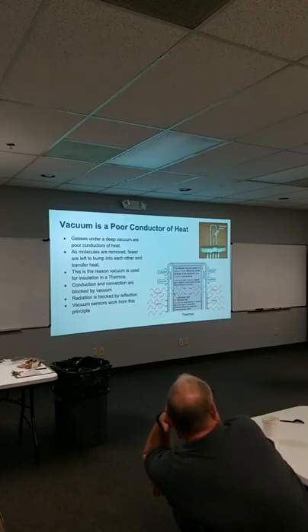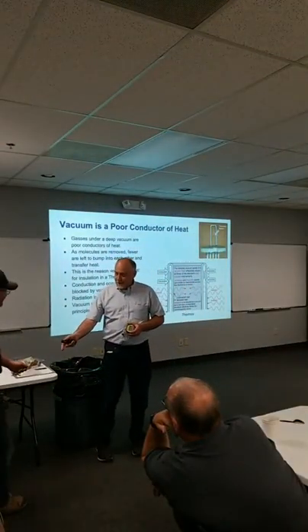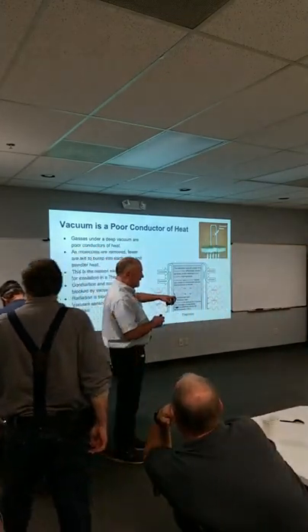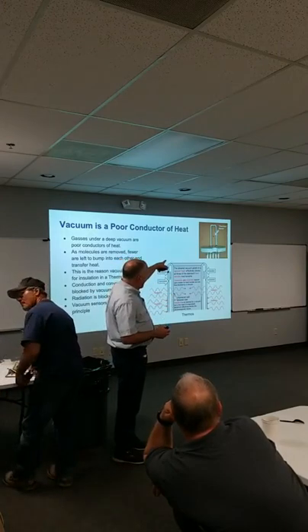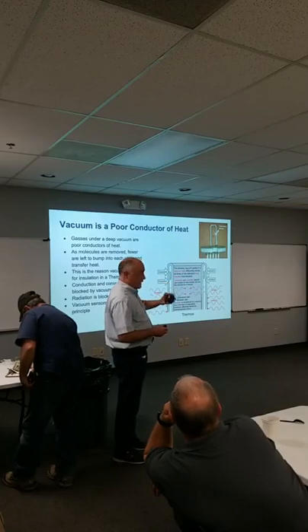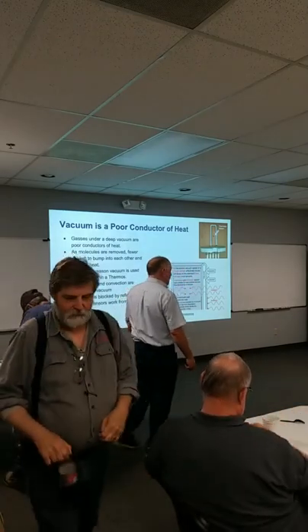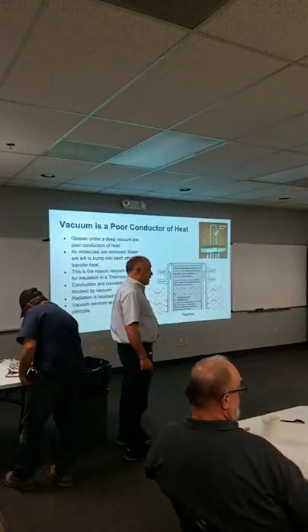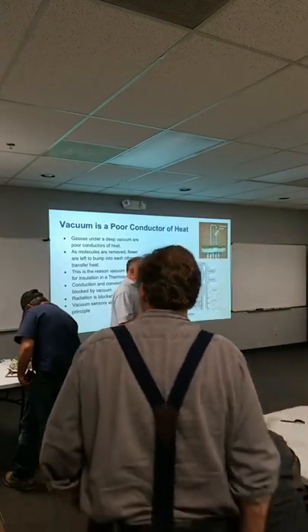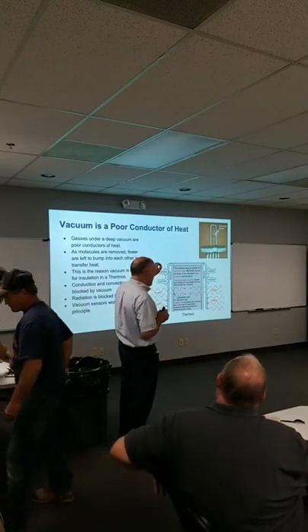Right, so if you're looking, oh, let's see, you brought your dues. Oh, absolutely. Thank you. If you look inside this hole right here, inside the hole is that sensor. If you look just inside here, you'll see the end of that. That little thermistor is about the size of a grain of pepper, and in your vacuum gauge it gets up to about 300 degrees Fahrenheit. So as soon as you turn on your vacuum gauge, that little bead is at 300 degrees Fahrenheit. If you touch it, it would burn you, right? Not for very long though, because it's very small, but it would hurt.